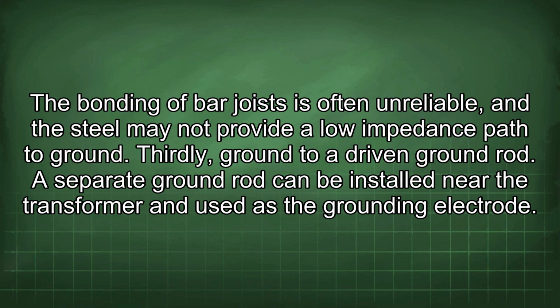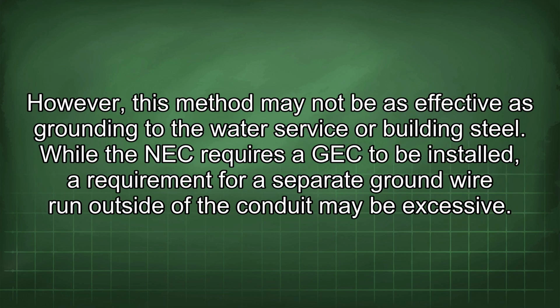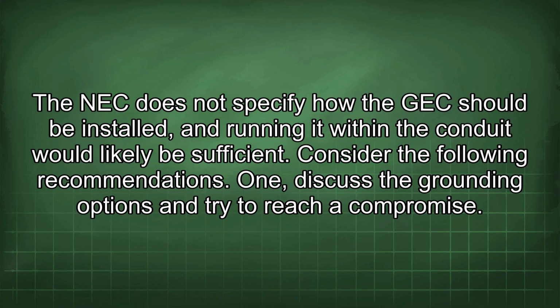impedance path to ground. Thirdly, ground to a driven ground rod. A separate ground rod can be installed near the transformer and used as the grounding electrode. However, this method may not be as effective as grounding to the water service or building steel. While the NEC requires a GEC to be installed, a requirement for a separate ground wire run outside of the conduit may be excessive. The NEC does not specify how the GEC should be installed, and running it within the conduit would likely be sufficient.